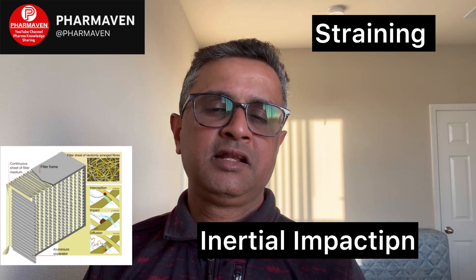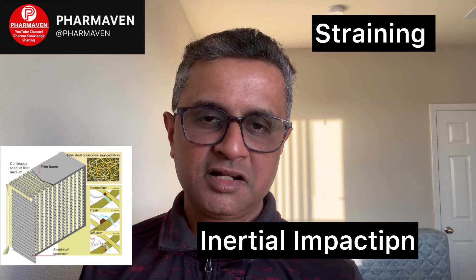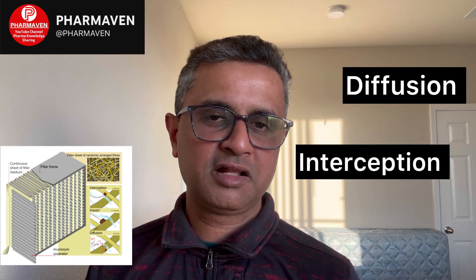So, a HEPA filter rated at 0.3 micron removes bacteria and particles even smaller than 0.3 micron through four mechanisms: straining, inertial impaction, interception, and diffusion. These are the four mechanisms by which a HEPA filter removes particles and microorganisms of various sizes from the air when air is passed through it.